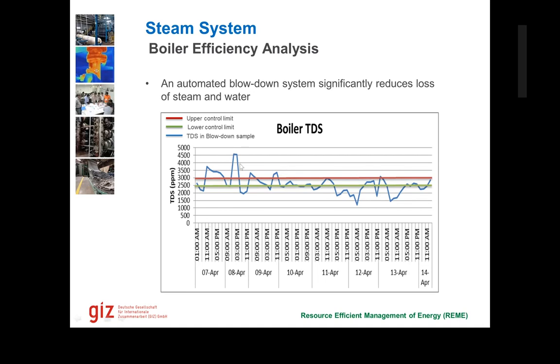So when we have higher TDS, that means we missed out on blowdown. Blowdown should have been done earlier. When we are near or below the lower control limit, that means we are doing too much blowdown, and then we are losing a lot of energy in blowdown as well. So if we have automated controls, then the blowdown would also be within the limits, and the quality of steam would also be within control.